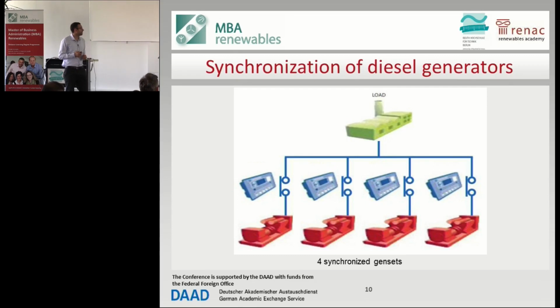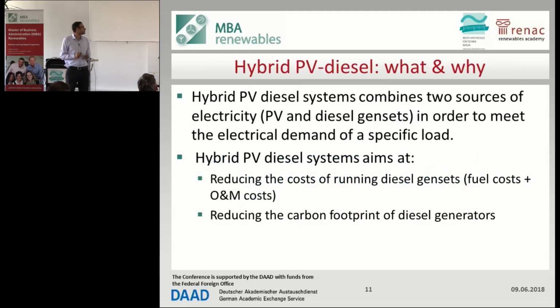This is just a diagram of how 4 diesel generators are connected together in synchronization. As you see, they are all providing the load with the required power. If the load dropped, one of them will switch off. As I said, there is the controller here. It's a very smart device. It will open this breaker and switch off this engine, for example. And then when it feels that there is another requirement, it will start ramping up the second diesel generator when it's required, to plug it in at the right time. It's very smart, and they really can manage the whole thing.